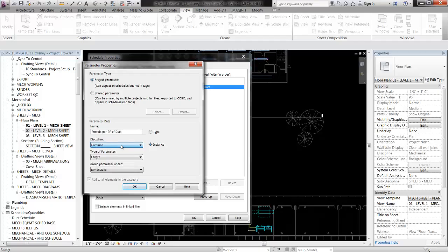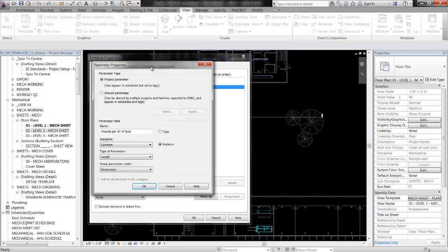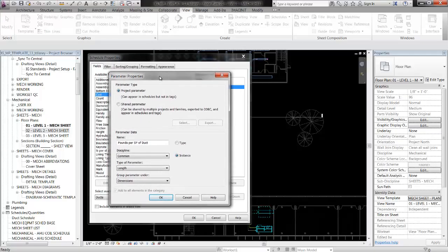Revit is fairly picky about units, so you have to make sure that your units match up, otherwise it will give you an error and not let you do what you want. So your options are either make the units work out or sort of hack them and make them not work out, but you know what they are, which is a method that I don't recommend. It'll tell you, you have 4 square foot and you know that means pounds. Just don't go there. Try to make the units work out. So, okay, we have pounds per square foot of duct.